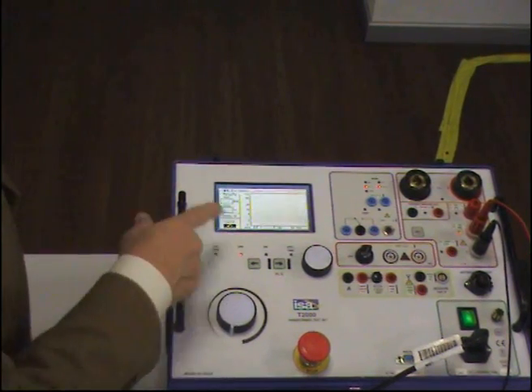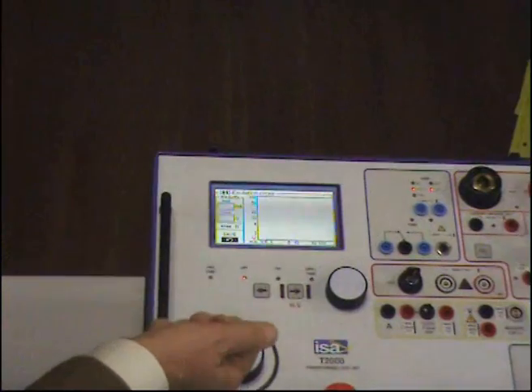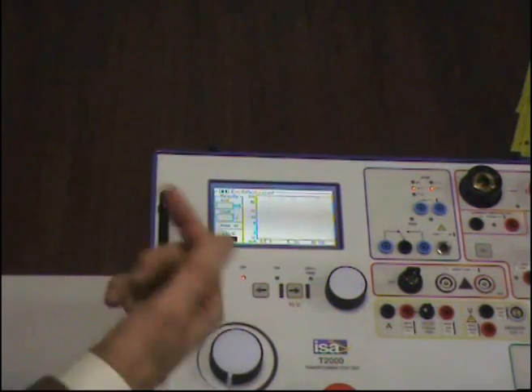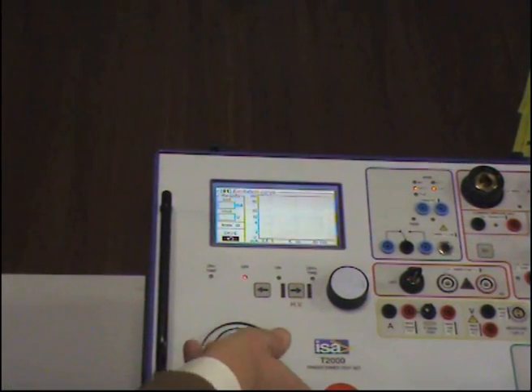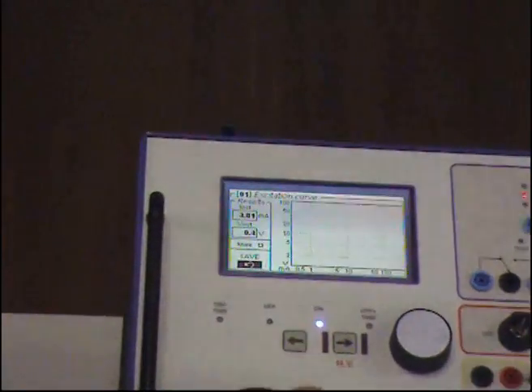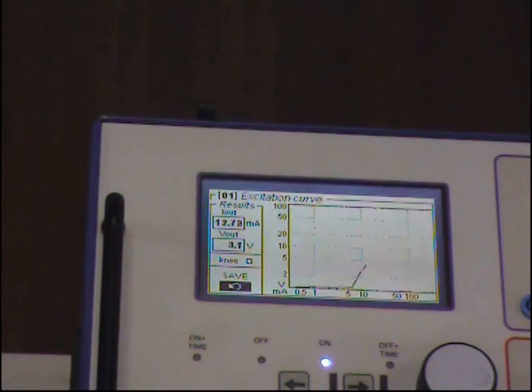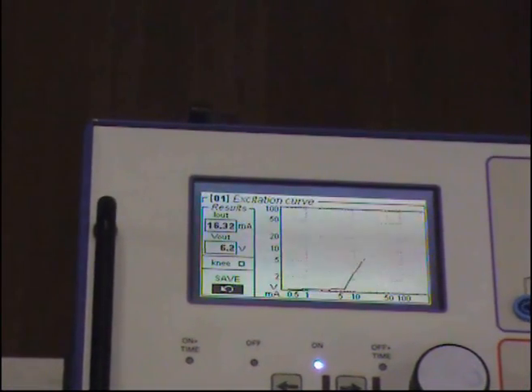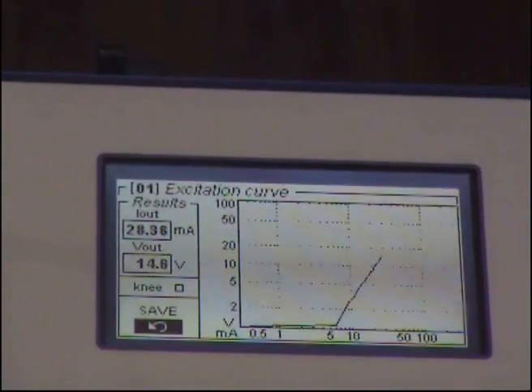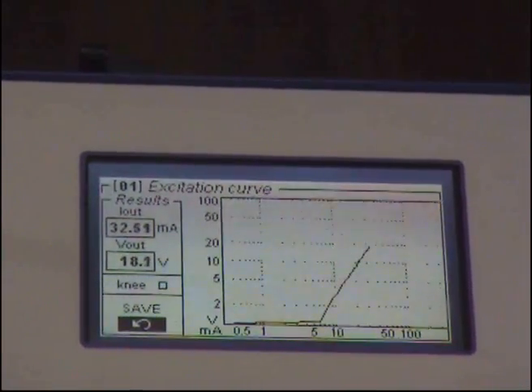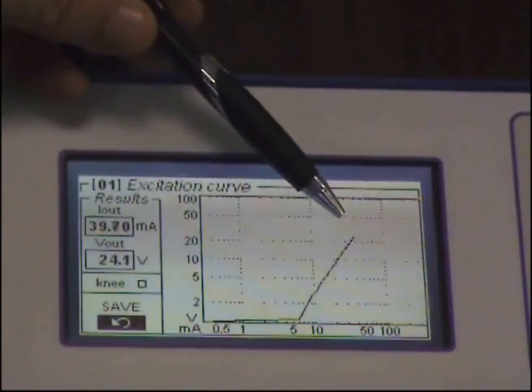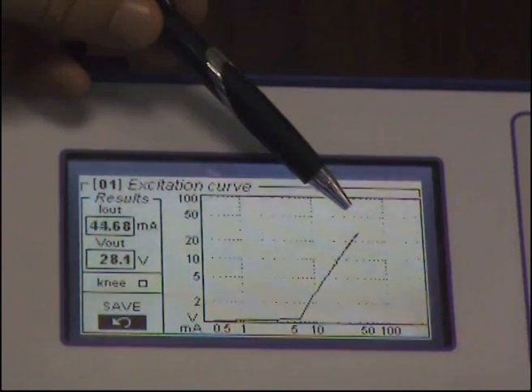The test set automatically recognizes the knee point given the IEC definition while you are going down with the current. I press on and go up — I am quite slow. This operation should last about 30 seconds, if not one minute. You can see we are now in the linear part where the voltage we are applying is causing a linear change in the current.